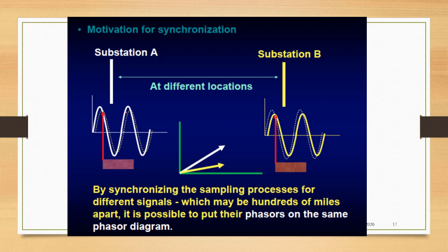So you can see here the synchronized measurement in substation A and substation B. These are different locations at a distant place, and by synchronizing the sampling processes for different signals at substation A and B, which may be hundreds of miles apart, it is possible to put their phasors on the same phasor diagram.